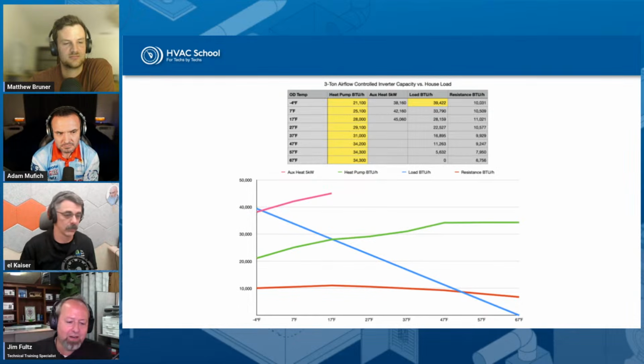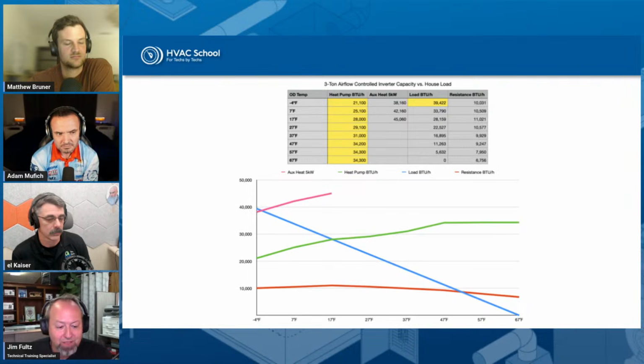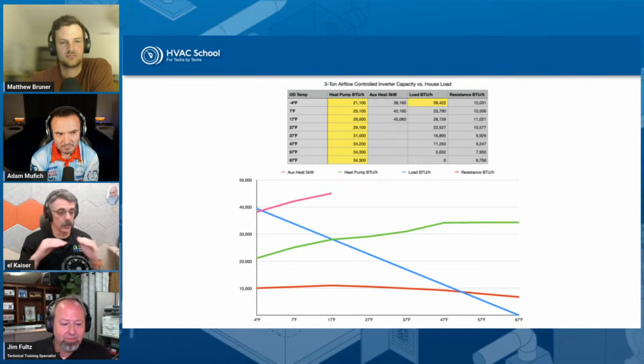If we were doing water to air, the bottom line would be whatever your well temperature or water incoming temperature is. It wouldn't go from 67 down to -4. It would be a constant 58 or 55 or whatever temperature your water is. So that number would never change. Well, it would if we're looking at the house slope. The load would change; the load slope, you would still have that there. But your other side of the refrigerant system, you're right, and I'm going to disagree with you slightly there, Jim. It will change slowly over the year, but it's not going to change drastically and immediately in the same way that air does.